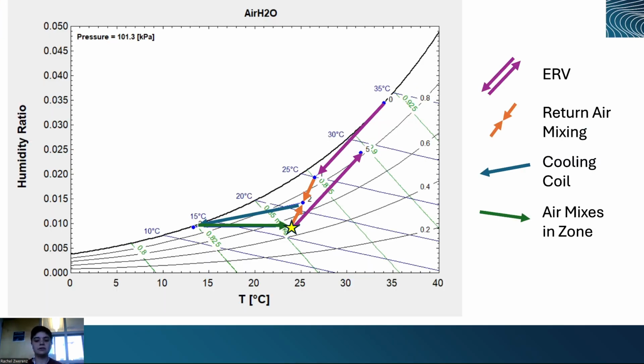So while we didn't necessarily do any hard calculations as far as the changing loads throughout the year, we did want to sort of go into the psychrometric chart and graph whether or not this was feasible. So if you look along the purple lines, we have the exchange between the entering outdoor air and the exiting exhaust air. And then that air goes down, mixes with our return air along the orange lines, cools along the cooling coil, and then that green line is the air mixing inside the zone. And that gets us towards the yellow star at the middle, which is within that comfort zone.